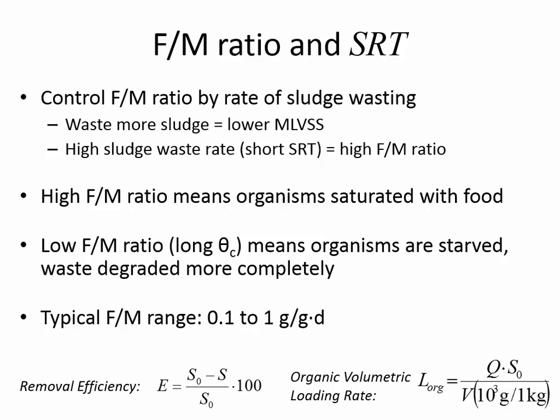The volumetric loading rate for organics is the inflow substrate concentration times the volumetric flow rate, divided by the volume of the aerator, and since all of these units would already be in terms of grams per day, it puts in the conversion for grams to kilograms, so that the organic volumetric loading rate is in kilograms per day when you make that conversion.